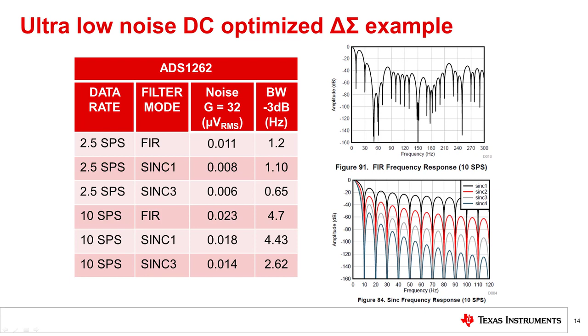Also, it should be emphasized that the lowest noise option in this example has a total integrated noise of 6 nanovolts RMS. This is incredibly low noise, as converters and amplifiers can have total noise in the microvolts range or higher. Of course, this makes sense when you consider that the bandwidth is only 0.65 Hz. So for this example, the converter is optimized to measure a very low frequency signal with minimal noise error.